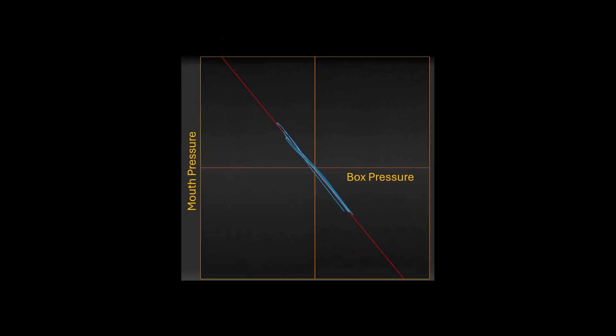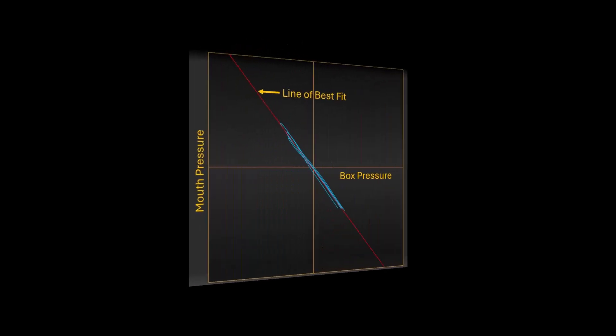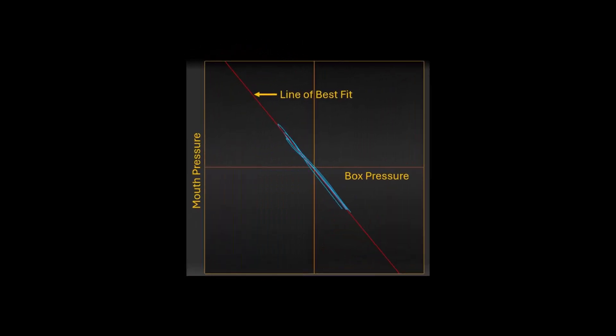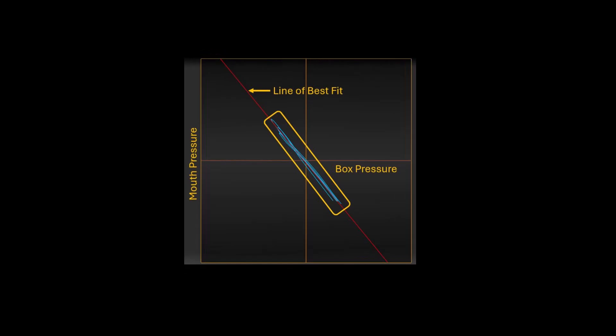we close the mouth shutter and ask the subject to gently pant. The tracing that is displayed measures mouth pressure over box pressure. The solid red line that goes through the tracing is called the line of best fit. The computer uses all of the data points from the tracing and places the line of best fit through the average of those data points.